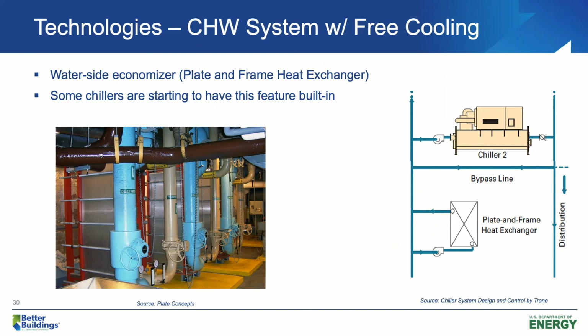Another technology is waterside economizer. Basically, the idea is that when the outdoor air wet bulb temperature is very low, probably the water temperature from the cooling tower is cold enough to make chilled water or pre-cool chilled water using plate and frame heat exchangers. Some chillers are starting to have this feature built in, and you do not have to buy and install a plate and frame heat exchanger.